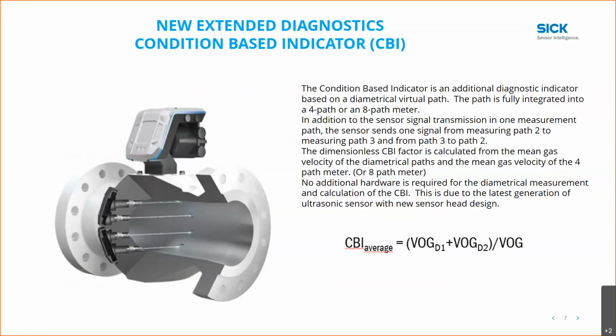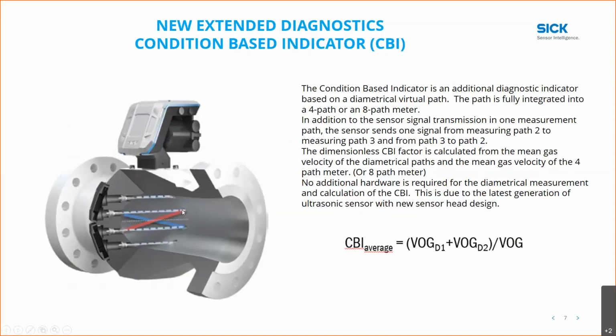What SICK has done in this next generation of meter is we now have something called the condition-based indicator. One of the things that we discovered by redesigning the transducers, we're able to actually measure the signal going from path 2 to path 3, as you see here in this illustration. So now we can measure the signal going between this cross-sectional area and this one here. So in essence, what we have is a virtual path that can measure the velocity through the center of the pipe.